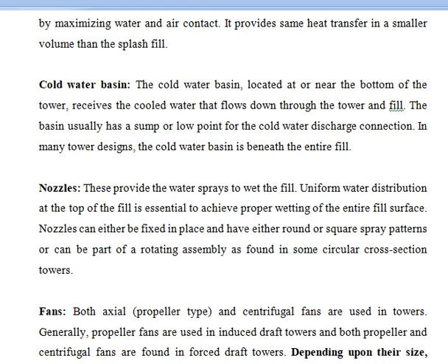Nozzle: these provide the water sprays to wet the fill. Uniform water distribution at the top of the fill is essential to achieve proper wetting of the entire fill surface. Nozzles are fixed in place and have either round or square spray patterns, or can be part of a rotating assembly as found in some circular cross-section towers. The nozzles only provide the water spray.